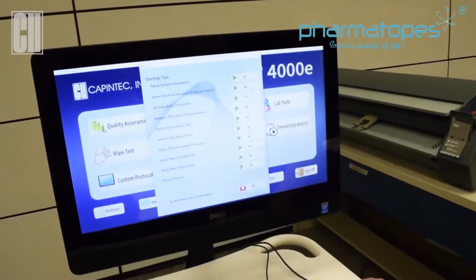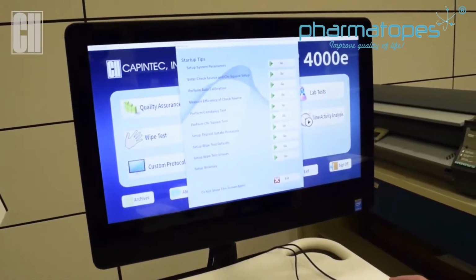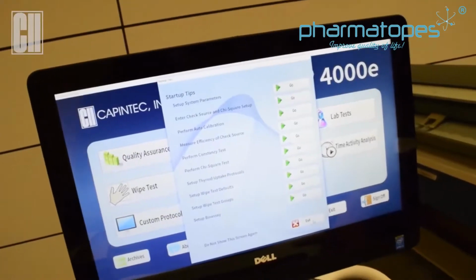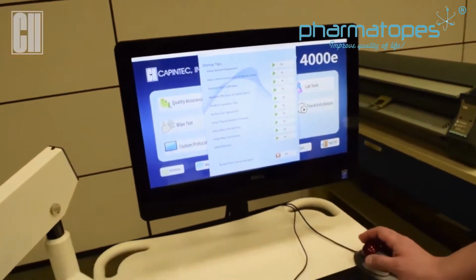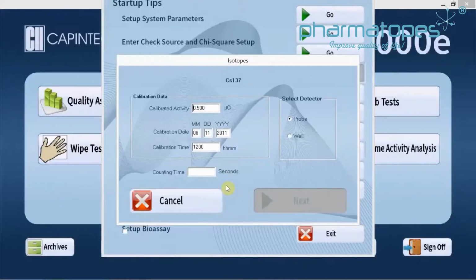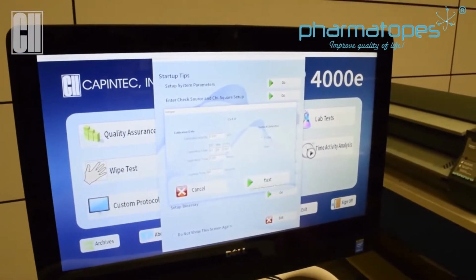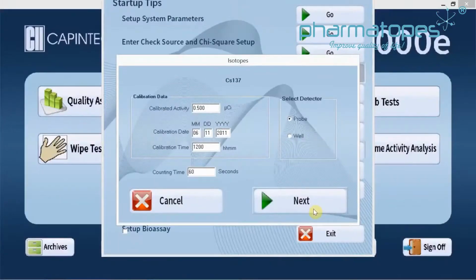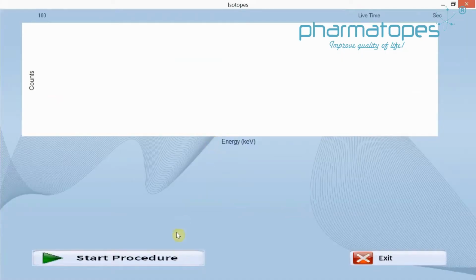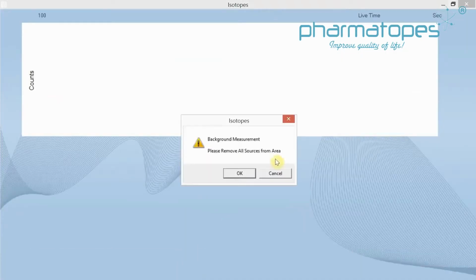To measure the efficiency of check source. What we do now is measure efficiency once again, but this time we're going to select it on the probe detector and have the counting time set at 60 seconds once again. Once the settings are in there and we verify the source information is still correct, click on next, and again start procedure. We're going to do a background of the probe.